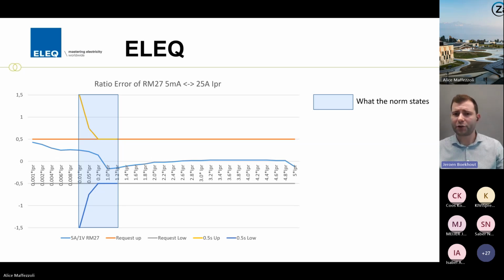Here you can see the ratio error of the RM27 from 5 milliamps to 25 amps primary. As you can see, we are really well within the band and really wide compared to what the norm states ELEQ should supply. Interestingly, at the beginning we are a bit more positive, which has to do with the excitation of the magnetization of the core. And at the end, at 5 times primary, you can see the core is already dipping a bit, meaning it's slowly saturating.